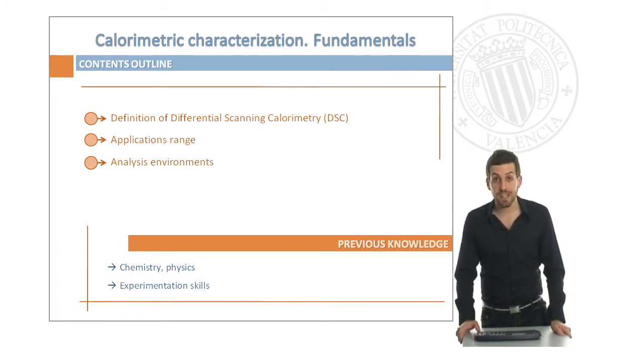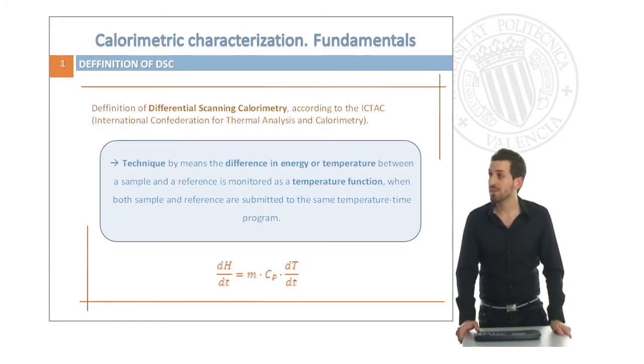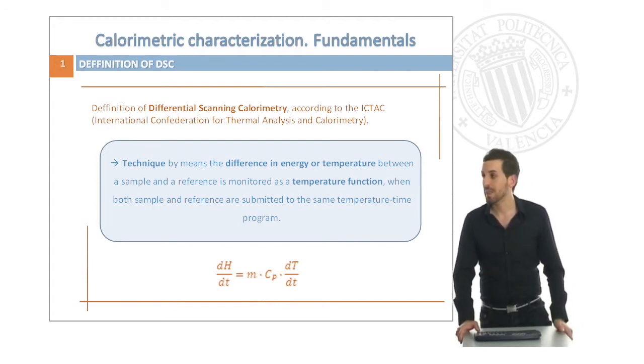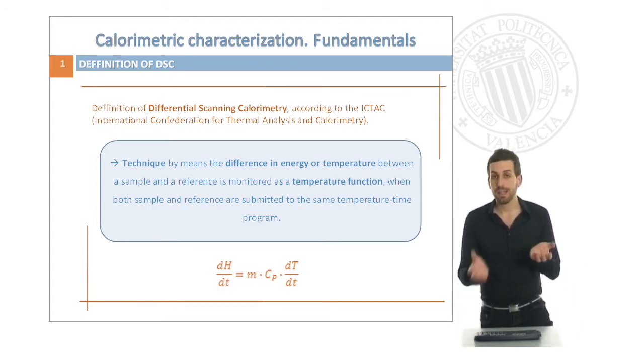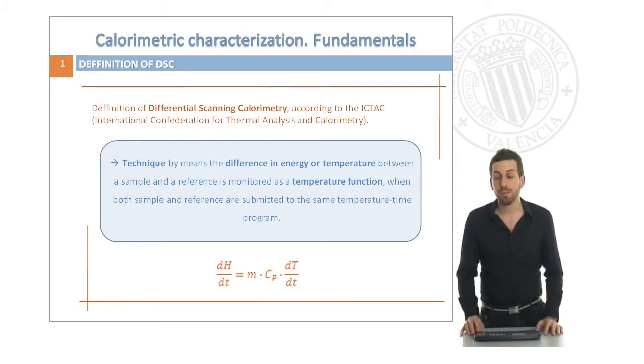Let's start with the definition of differential scanning calorimetry. According to the International Confederation for Thermal Analysis and Calorimetry, differential scanning calorimetry is a technique in which the difference in energy or temperature between a sample and a reference is monitored as a temperature function when both sample and reference are submitted to the same temperature program.